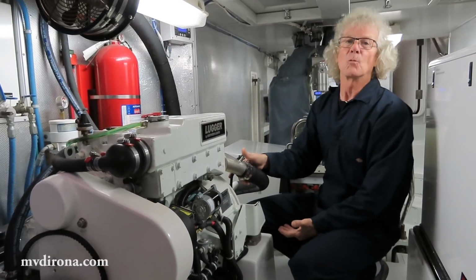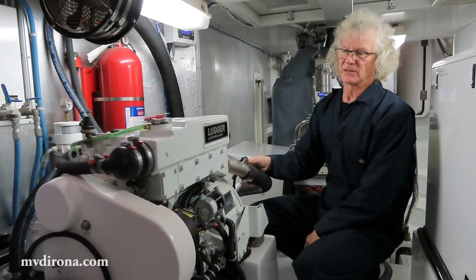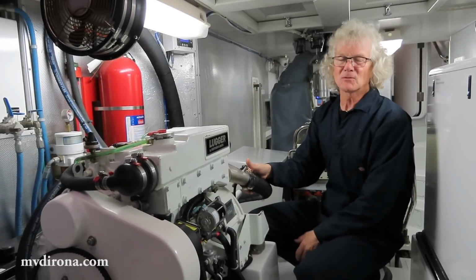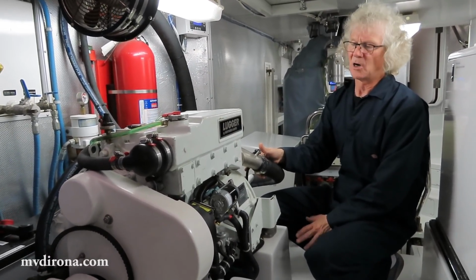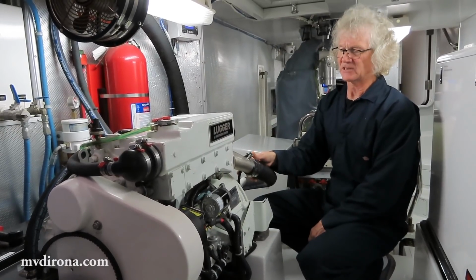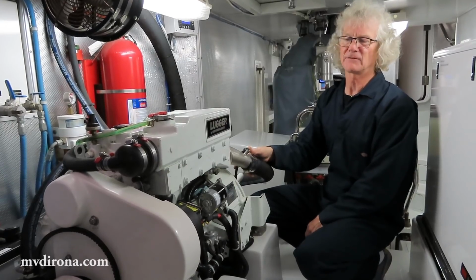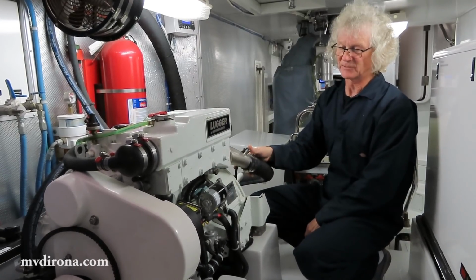So we know we need to do something with that. The question is, when do we need to do it? It's been making a little bit of noise over the past year and a half. It probably would go another year, almost certainly. But there is some risk that it eventually could catastrophically fail. And so you want to get to it before there's any risk of catastrophic failure disabling the system entirely.